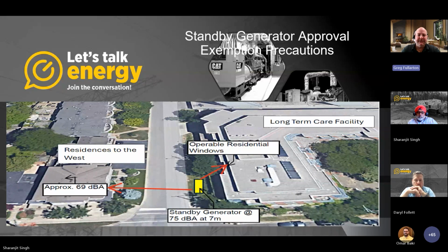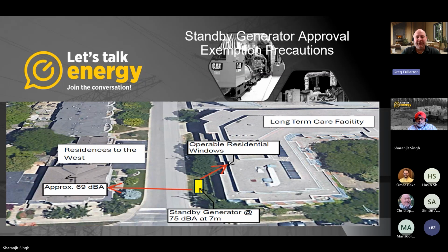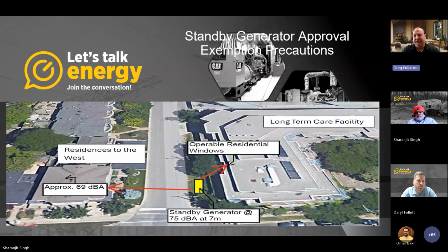The other thing that's happening here is this is a long-term care facility, and you have a lot of elderly patients on this west facade floor. And the administrative criteria, which is really all you can do if you're going to have a generator on the ground, the administrative criteria of having the windows closed during the periodic testing of the generator should work and should be valid, except you can't count on the patients in this long-term care facility to close those windows. They could be asleep and breathing in the contaminant emissions that are being pumped out by this generator and going into that facility. The administrative control of keeping the windows closed during testing, as long as staff at this facility take that seriously and make sure all windows and doors are closed during the periodic testing of that generator, that could work.